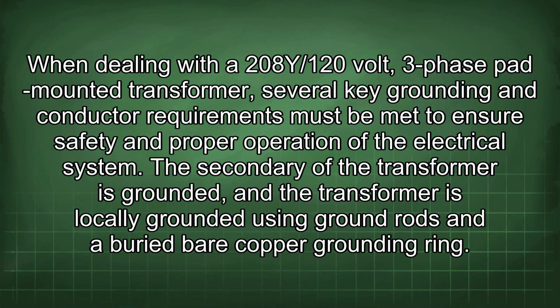When dealing with a 208Y/120-volt, three-phase pad-mounted transformer, several key grounding and conductor requirements must be met to ensure safety and proper operation of the electrical system. The secondary of the transformer is grounded, and the transformer is locally grounded using ground rods and a buried bare copper grounding ring.